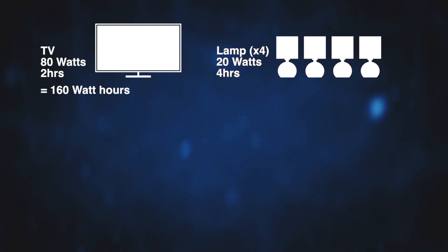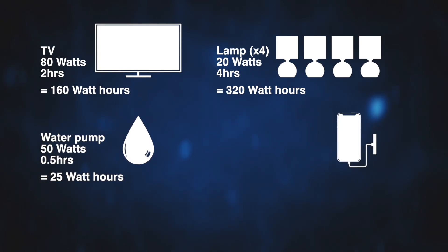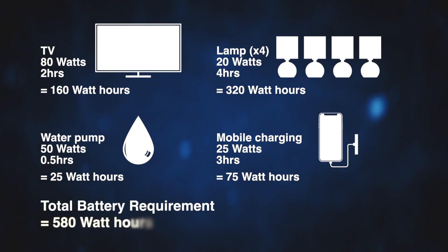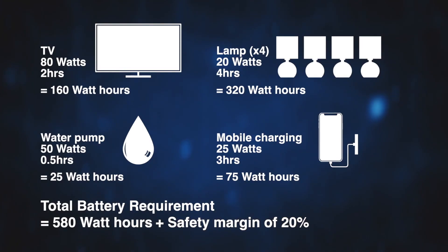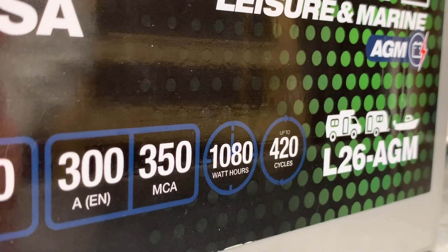For example: a TV rated at 80 watts on for two hours takes 160 watt hours; four lamps rated at 20 watts on for four hours takes 320 watt hours; a water pump rated at 50 watts for half an hour takes 25 watt hours; and charging a mobile device rated at 25 watts for three hours takes 75 watt hours. This gives a total of 580 watt hours. It is then advisable to factor in a 20% safety margin, giving a requirement of 696 watt hours.